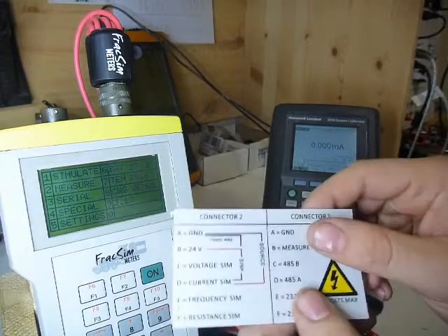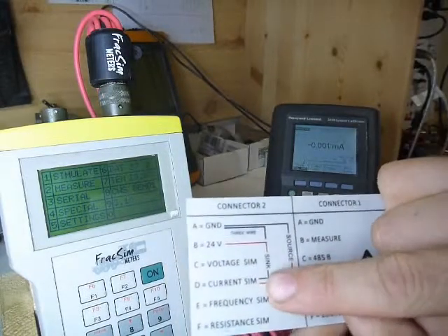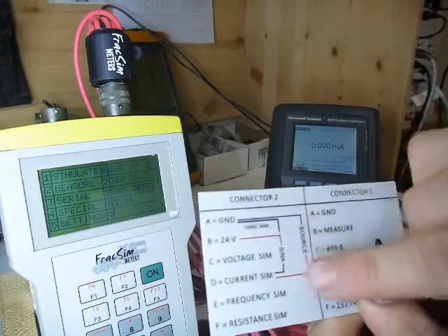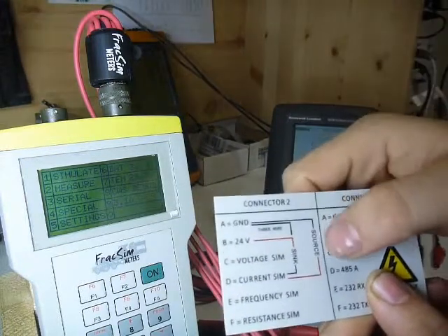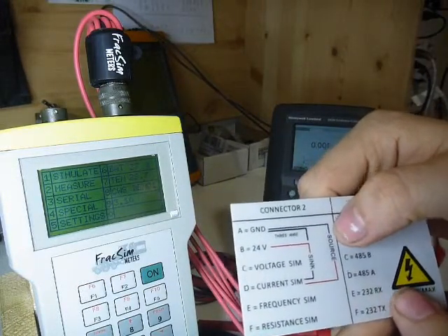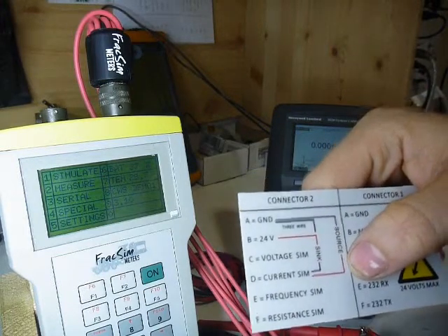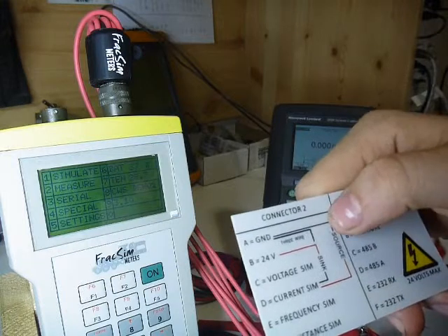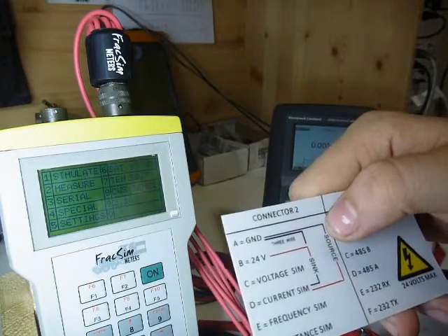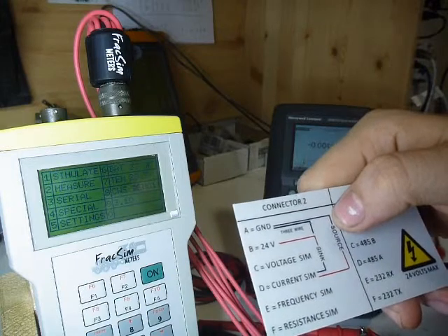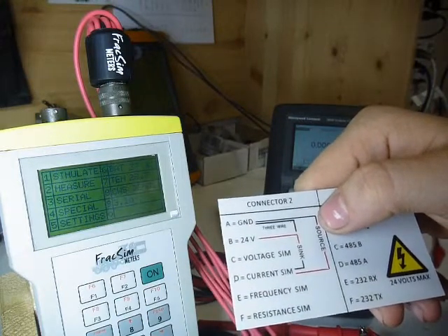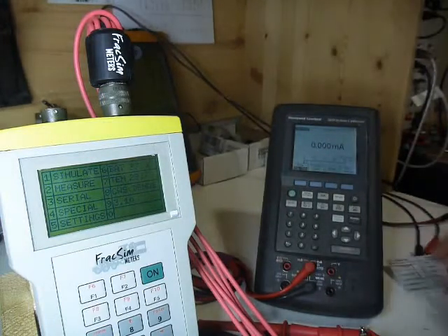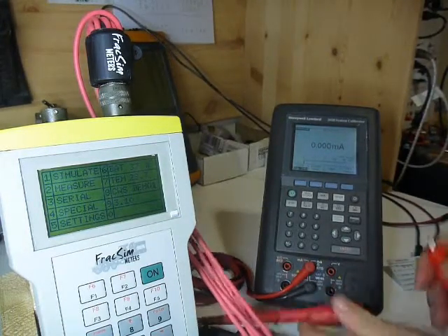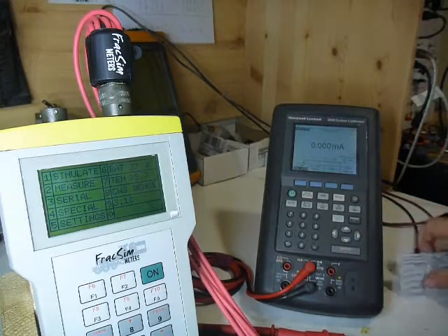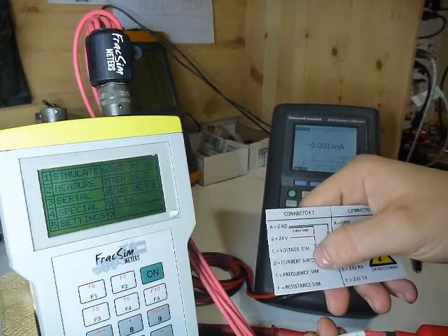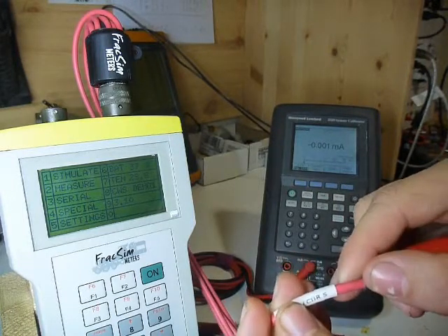So like we talked about, if you look at this card here, the sourcing, it shows we're going to use current sim and follow that around to ground. And of course the red and the black or the blue indicates red would be hot or power supply positive from the unit, and the darker, the black or the blue would be the ground on the unit. So it depends, of course, on the pinout on the unit you're working on. So for us, basically, I'm just going to find the current sim pin, and you can see it there matches up, it shows current sim right there.